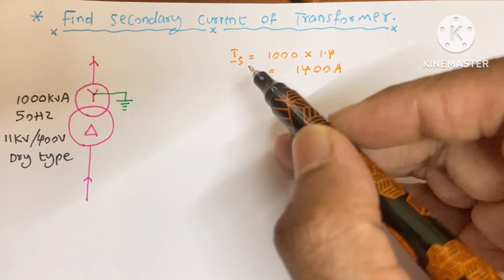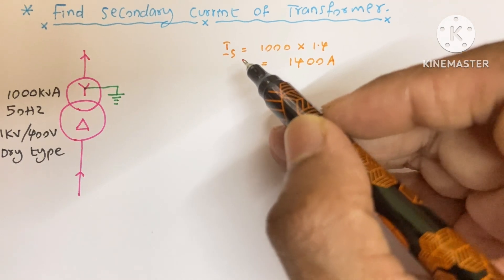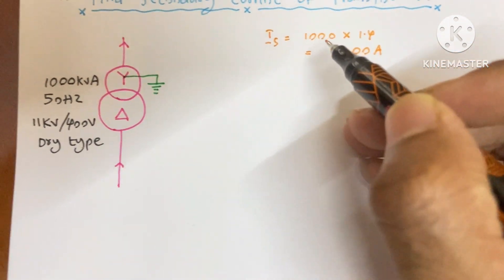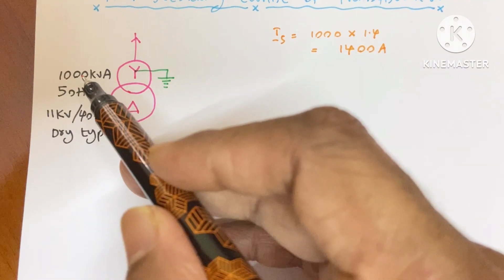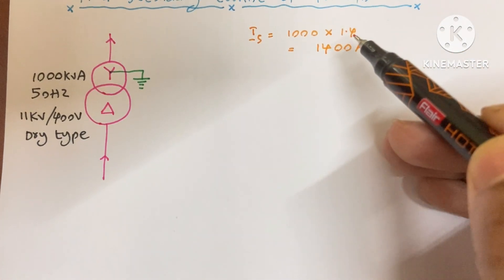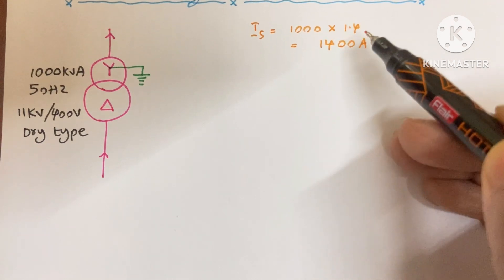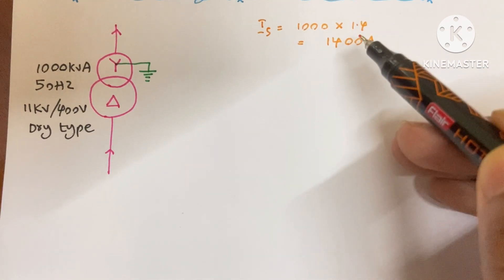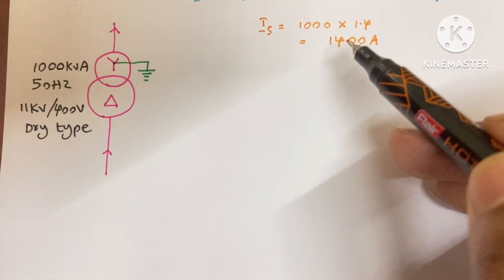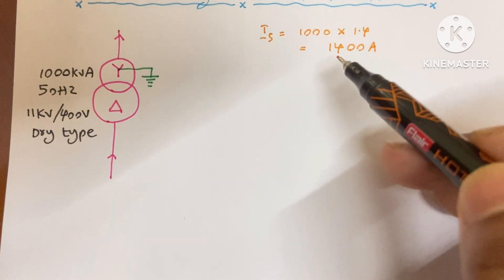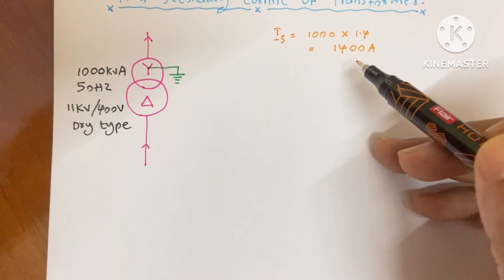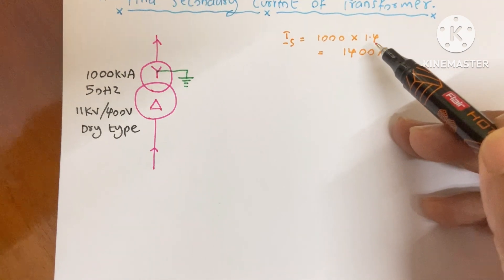This transformer's secondary current Is equals 1000 — this 1000 comes from the 1000 kVA — multiplied by 1.4, which is the magic value. So if you multiply these two together you get 1400 A. Now I will explain how we get this 1.4.